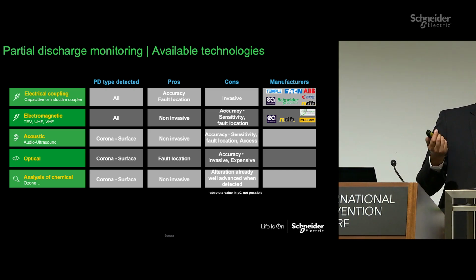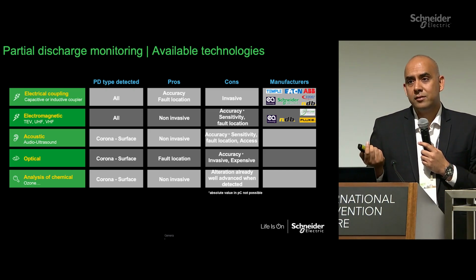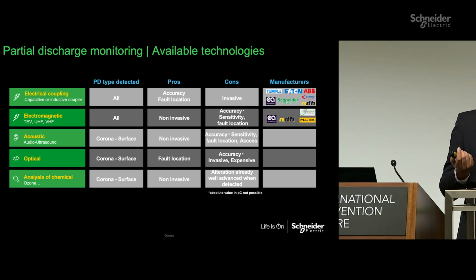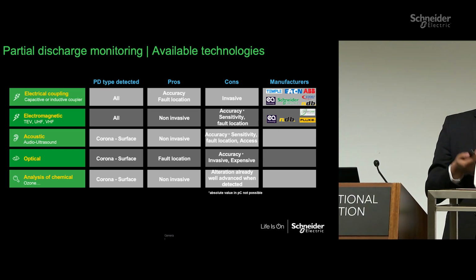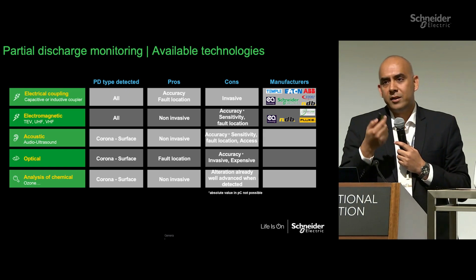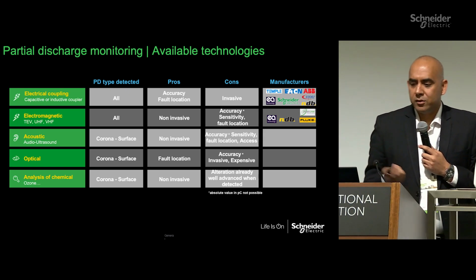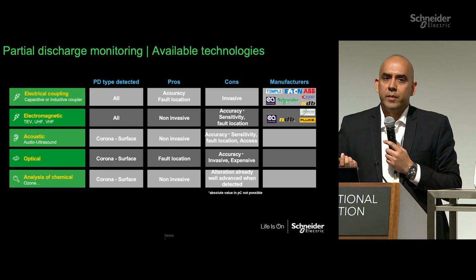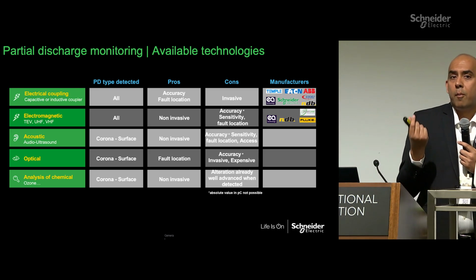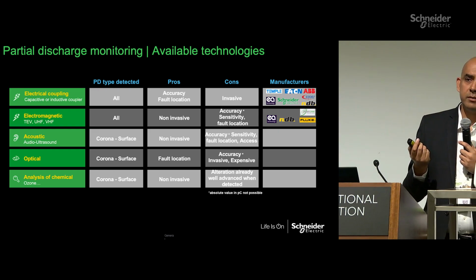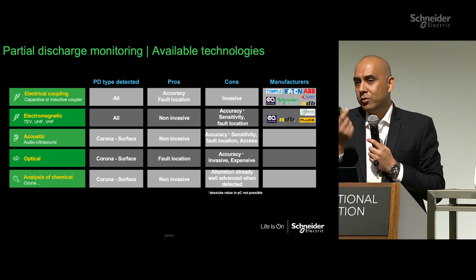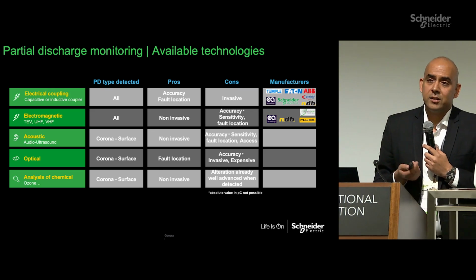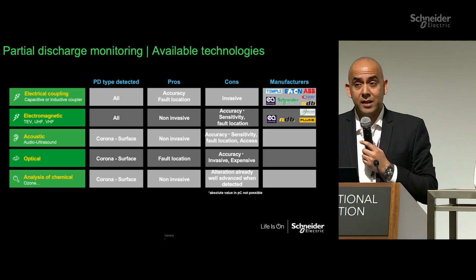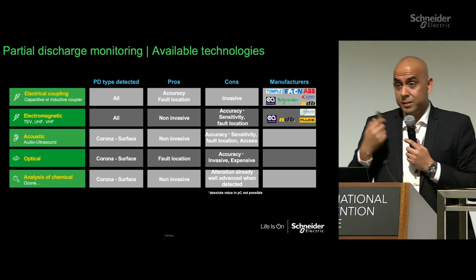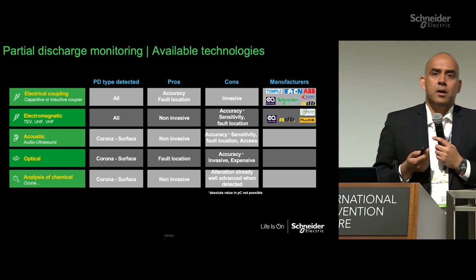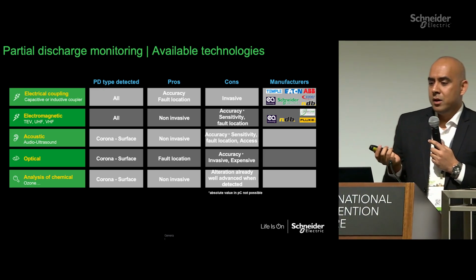So, of course, one very basic way is through monitoring of gases, chemicals, of course, ozone, but it's not very good because if the gas is there, that means automatically the discharge has already happened, the air is already ionized. So not the best of ways to measure partial discharge because you cannot mitigate the issue. Second is optically. Visually, you can have a camera to observe it. Again, not very good because it's only detecting one type or two types of discharges, and already the discharge has happened. The damage is already done. Third is sound measurement. It is used sometimes, again, limited application, not very accurate.